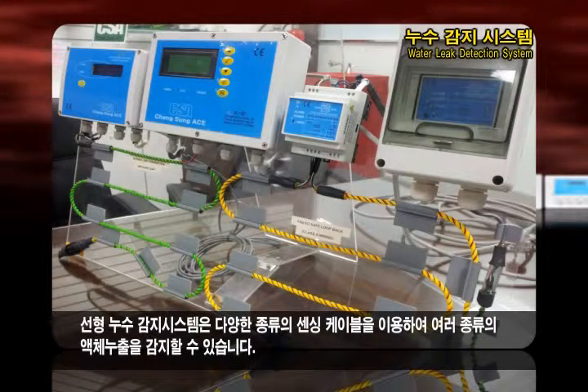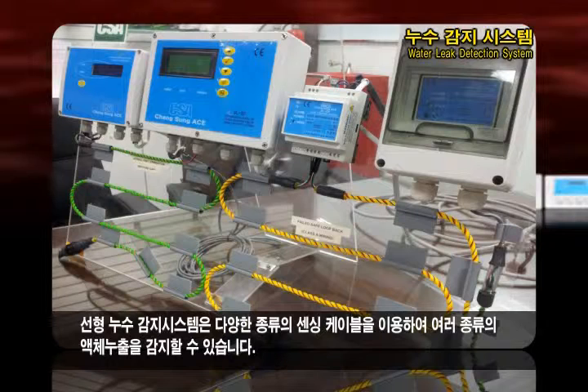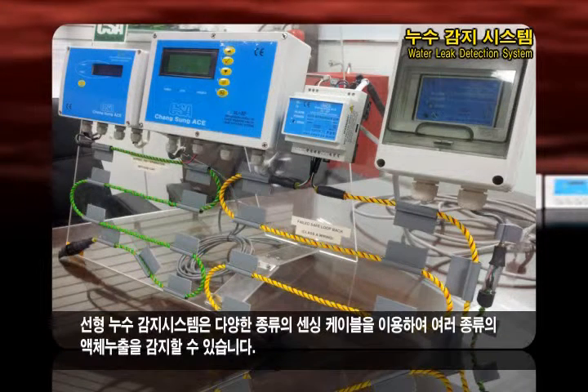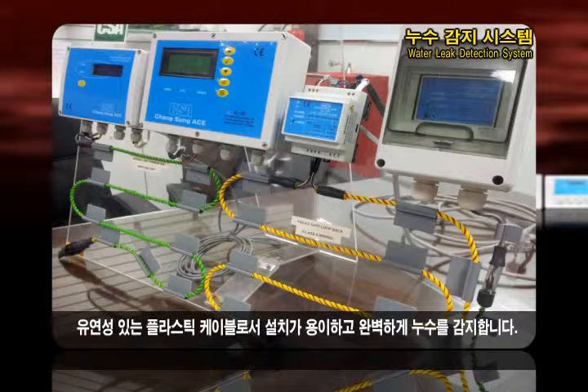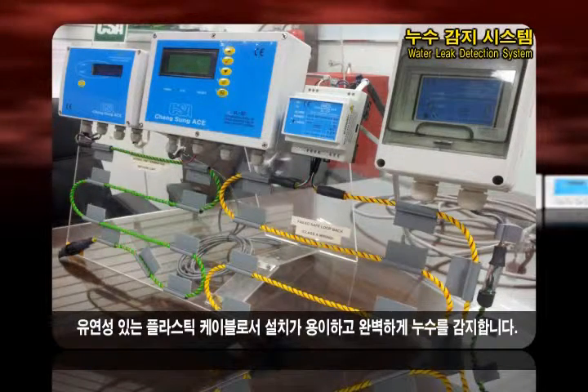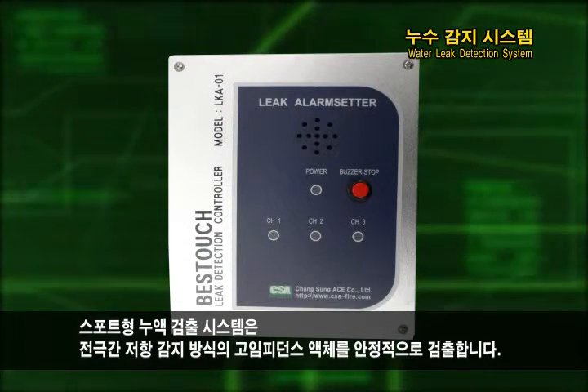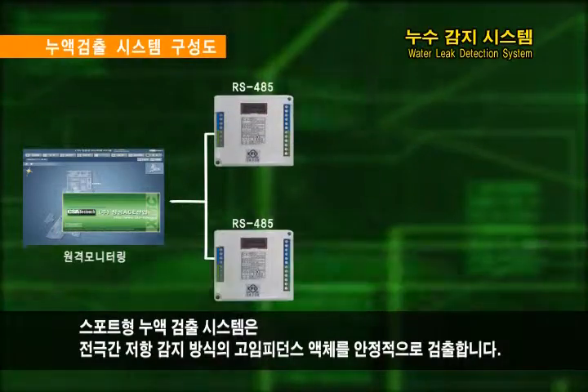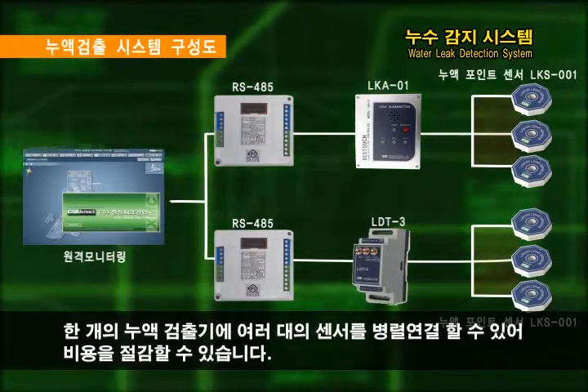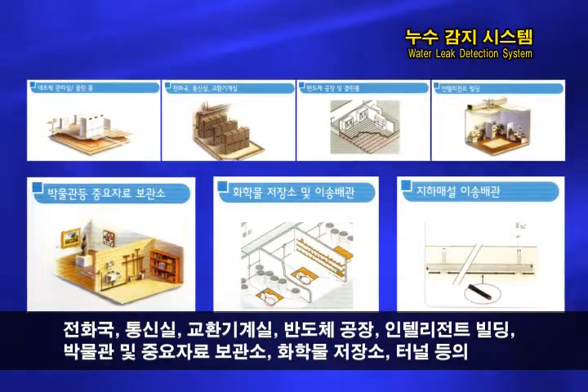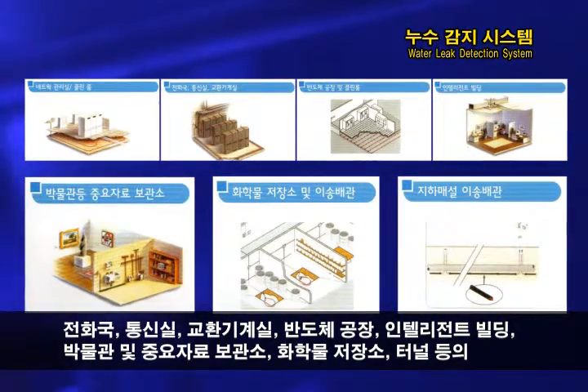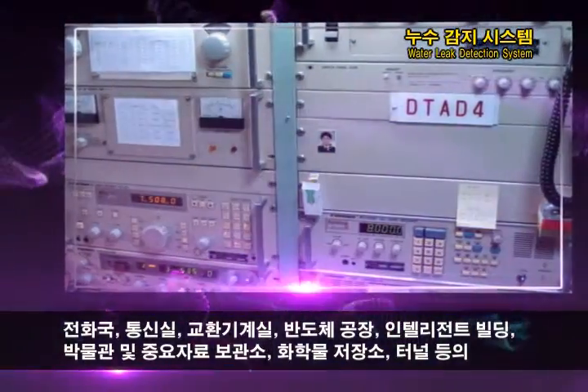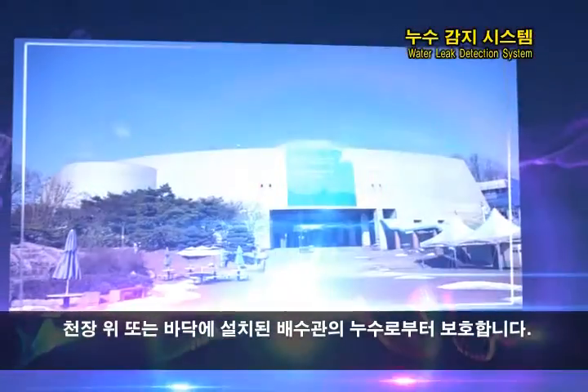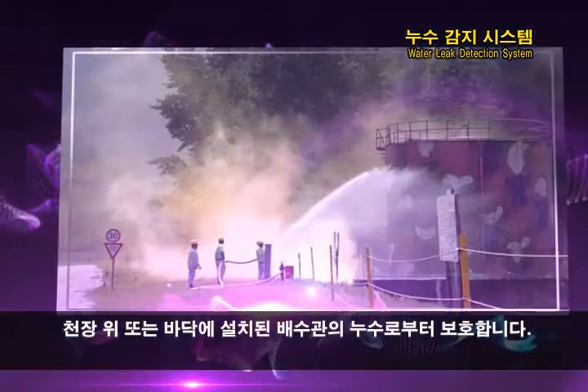The water leak detection cable system is designed to detect various types of fluid leaks by using different types of sensing cables. It is made out of flexible plastic cables for easier installation and is an effective system to detect a leak. Spot type leak detection system is designed to detect high impedance fluid by sensing inter-electrode resistance. Multiple sensors can be installed onto one detector, so it is also cost effective. This system detects leaks from plumbing and is suitable for many places such as phone service carrier centers, telecommunication centers, control rooms, semiconductor manufactories, intelligence agency buildings, museums, and secured storage rooms for sensitive documents or hazardous chemicals.